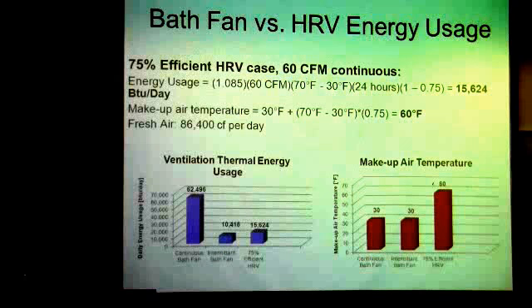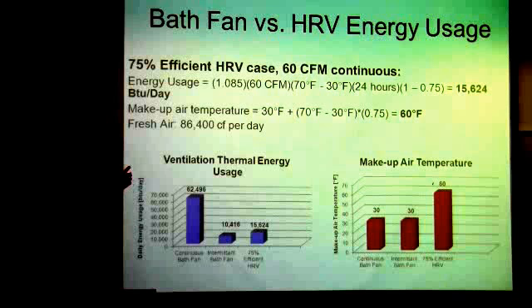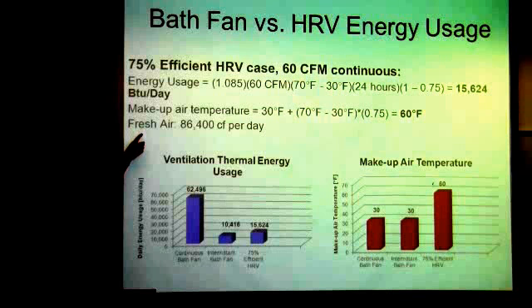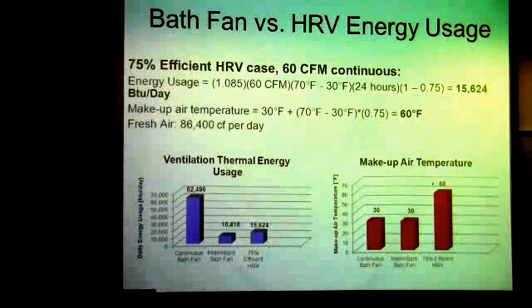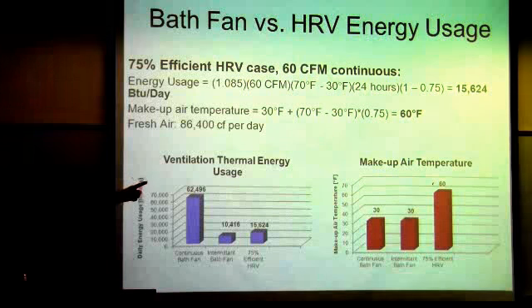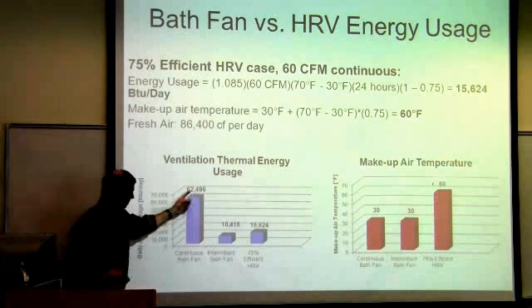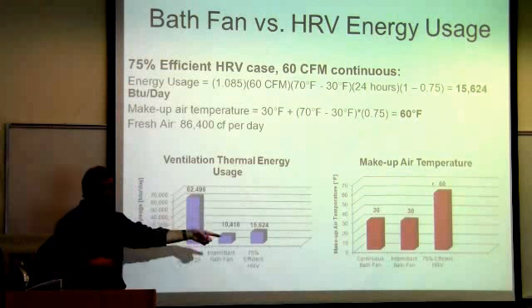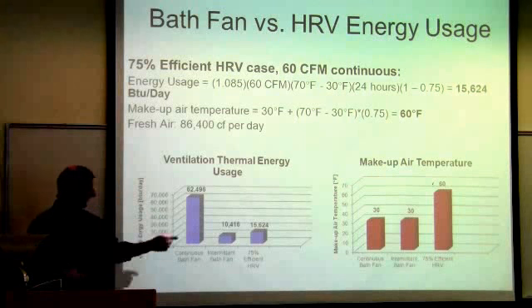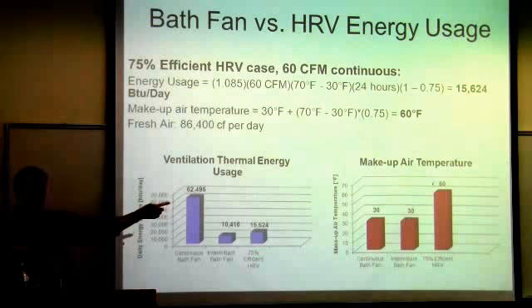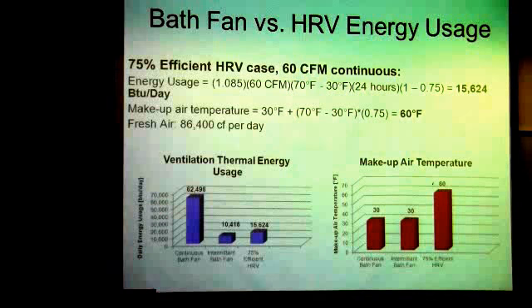So if you have a 75% efficient HRV running 60 CFM continuous, you're still getting the 86,000 cubic feet per day, which meets your requirement. But you're only having to use 15,000 to heat it versus the 82,000 if you weren't using an HRV and pulling the same flow rate in. And your makeup temperature is 60 degrees, and that's why.